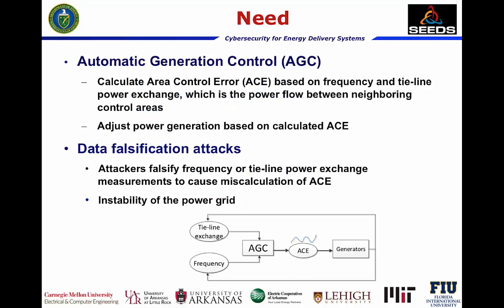Automatic Generation Control is a key control system in the power grid. Based on the measured frequency of a control area and the measured tie-line power exchange with neighbor control areas, it periodically calculates the area control error and adjusts this control area's power generation based on the calculated ACE.